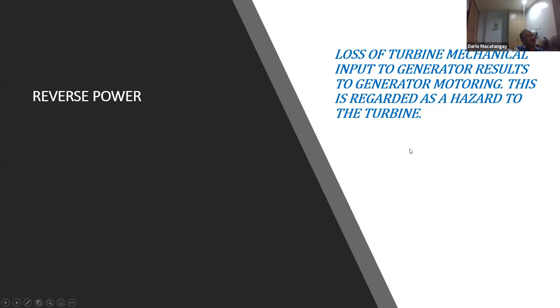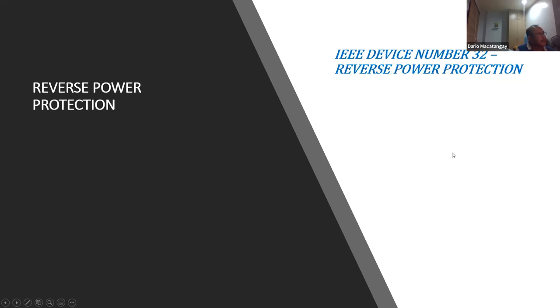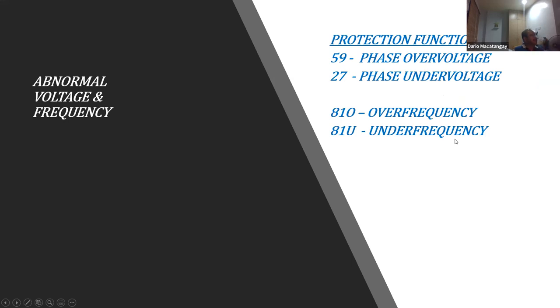Loss of mechanical input to the generator is, again, reverse power. It's generator motoring, and you're using reverse power protection for this. We get the voltage and current input and determine the setting in reverse watts. That's device number 32, reverse power protection. The last one is abnormal voltage and frequency. Of course, we have phase overvoltage and phase undervoltage, 59 and 27, and frequency 81, over frequency and under frequency.